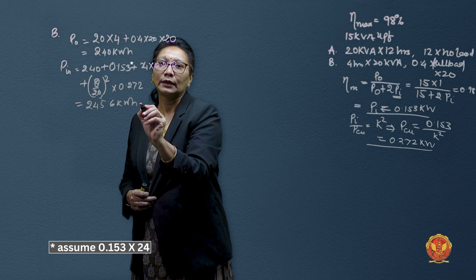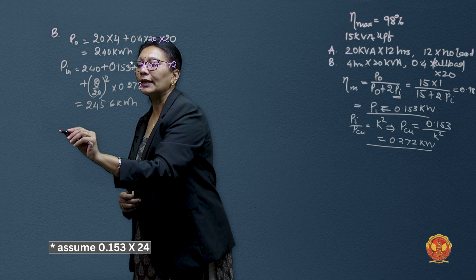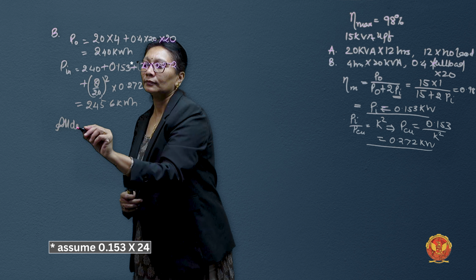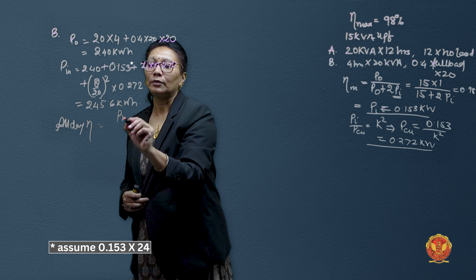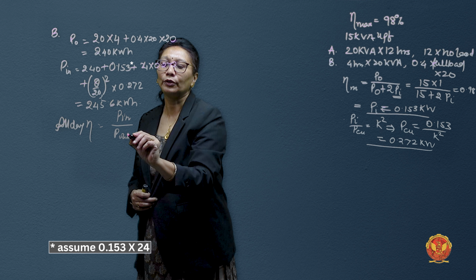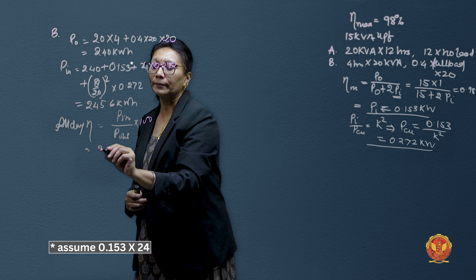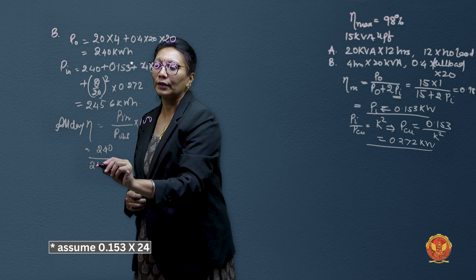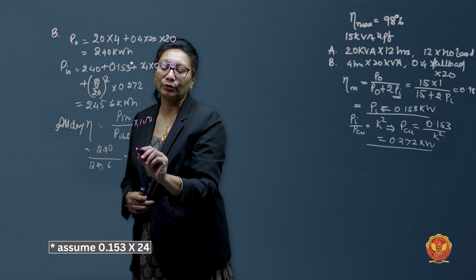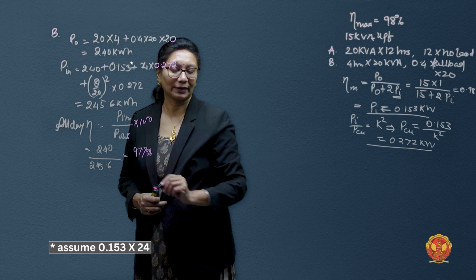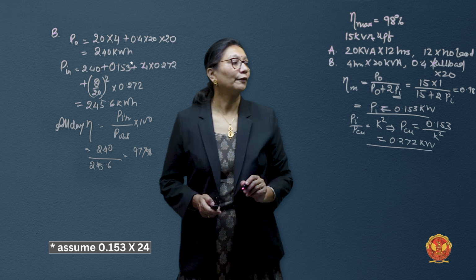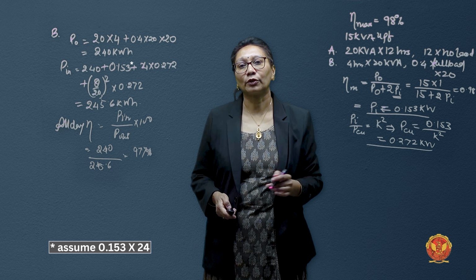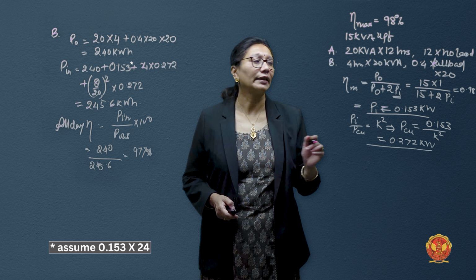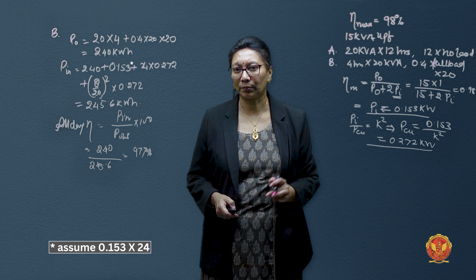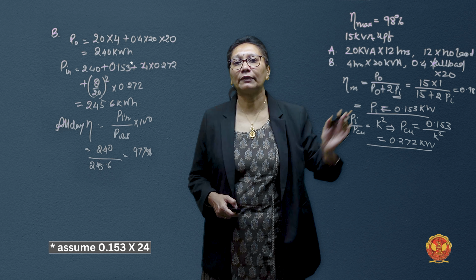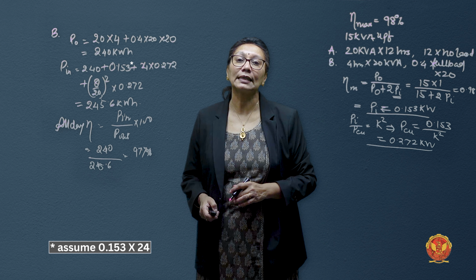This gives us P input as 245.6 kilowatt hour, and all-day efficiency as P out by P in in kilowatt hour into 100, which is 240 divided by 245.6, coming out to 97.7%. So we can observe there is a difference in both all-day efficiencies. When the transformer was at no load for 12 hours we had 97.2%, while when the transformer is delivering some load all day, its all-day efficiency is 97.7%.